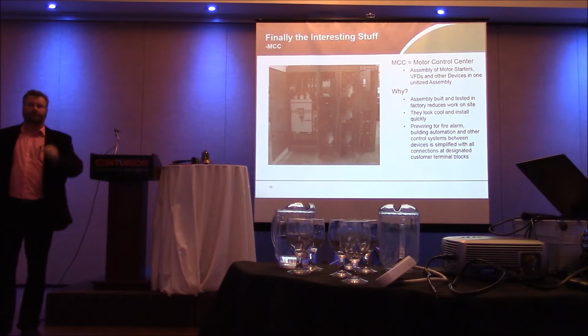So we love MCCs. So you're going to get pushed, especially if you have mechanical loads that are scattered all over the place, for me to do one electrical room, put an MCC in it, and run wire all over. It may not be the best solution for you, but it's the best solution for me. And this is where there's going to have to be a dialogue between you guys and the electrical guy about how you're going to approach that. Because for you, it may be better that there is a starter or a drive located closer to your motor.